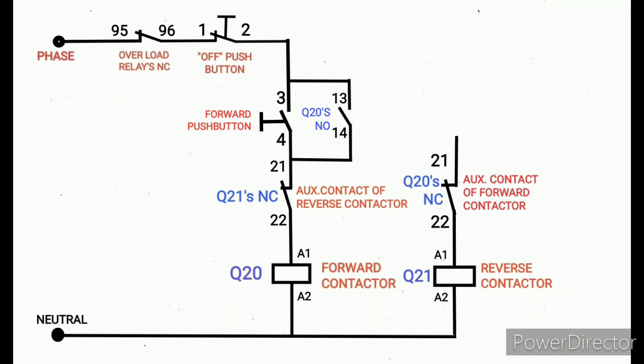Next we're going to draw reverse push button. This reverse push button is in series with Q20's NC and the reverse contactor coil terminal A1. We need to connect the main phase to the off push button second terminal.